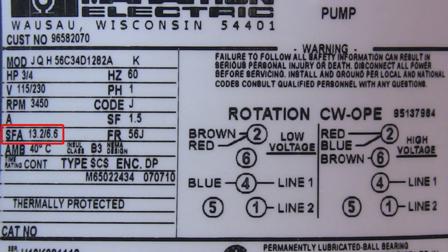The amp draw indicates the amperage flow at the motor's low and high voltages. In this example, the motor will draw 13.2 amps at 120 volts and 6.6 amps at 230 volts. Thermal protection. This indicates the motor has an internal device which monitors the buildup of heat and shuts the motor off if it gets too hot. A motor not having thermal protection means it needs some type of external circuit protection like a fuse. Motors without thermal protection should never replace motors with thermal protection.